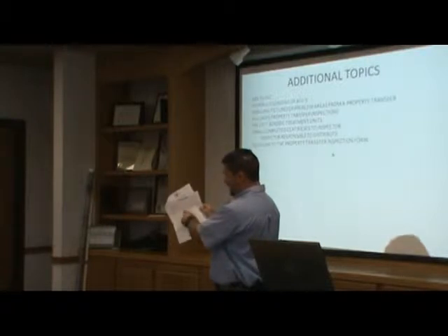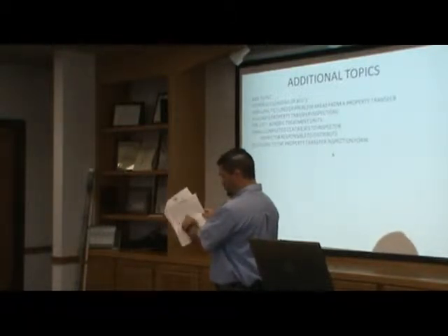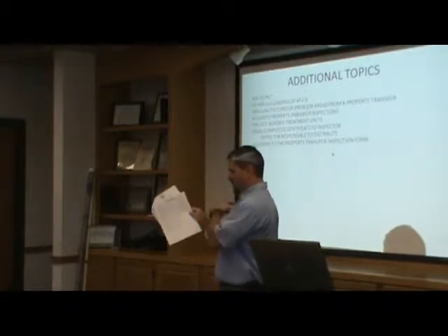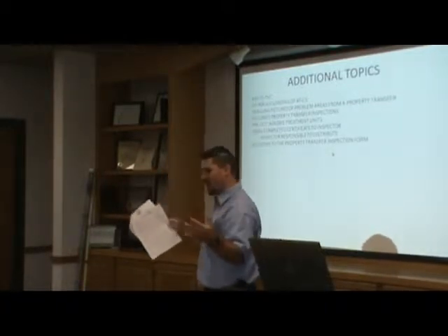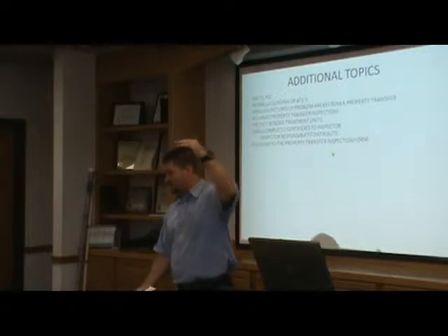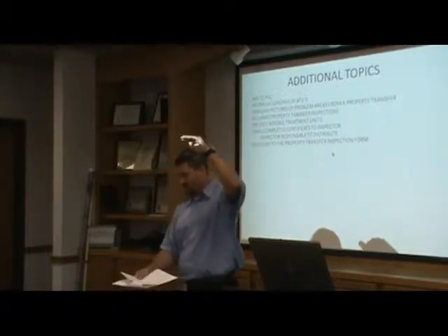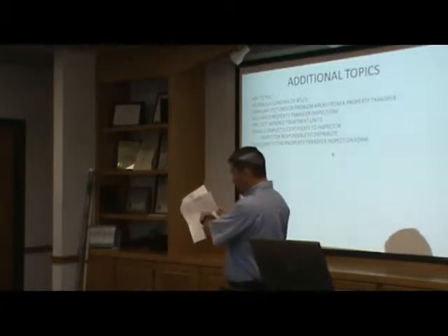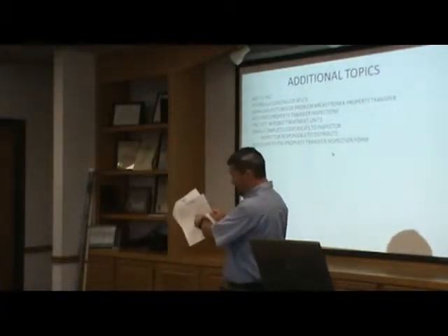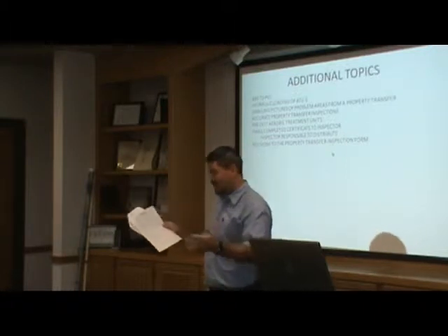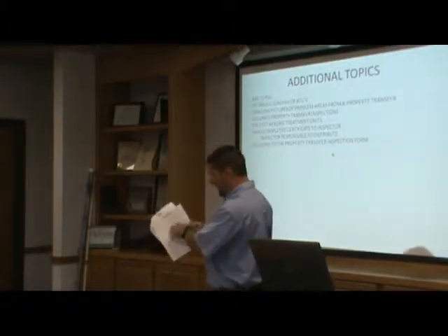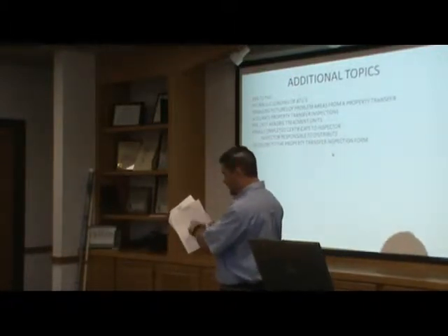I did change water level in, pre-hydraulic, post-hydraulic. You guys know tank 1, tank 2. When I do inspections, sometimes you take it from the riser because the tank is 3-4 feet deep and you can't really read what it is at the top of the tank, which is what we had before. So if you take it from the top of the riser, circle the riser. Tank lid, inlet, some people still look at the inlet. Just circle that. That way we're all on the same page of what we're referencing.